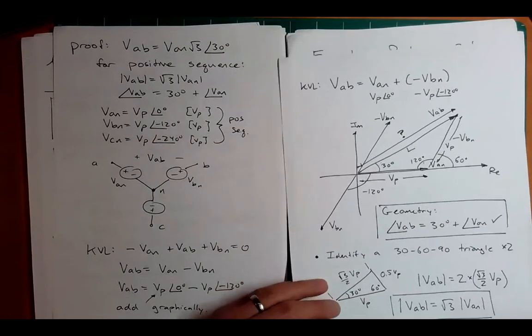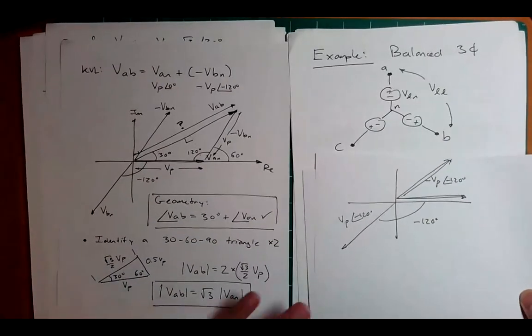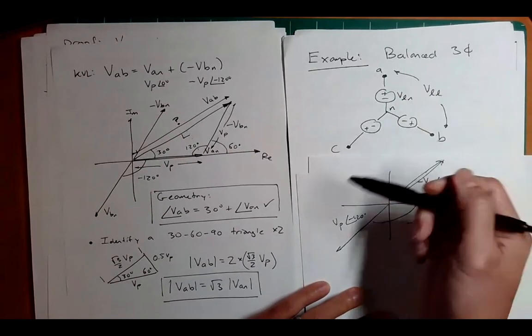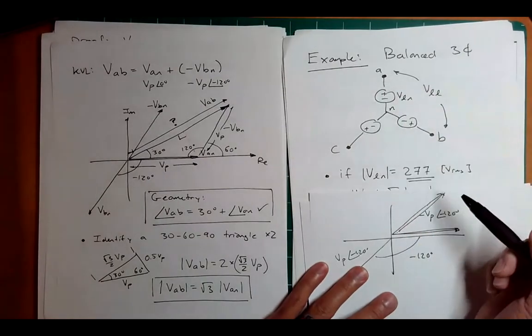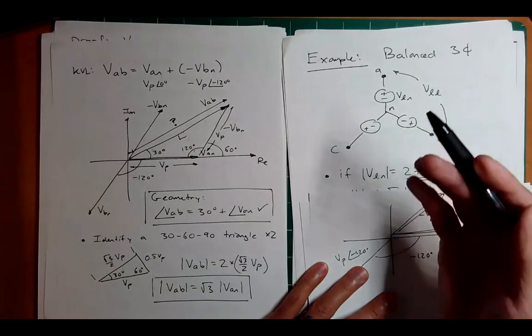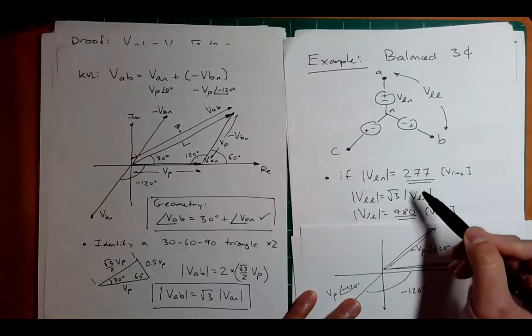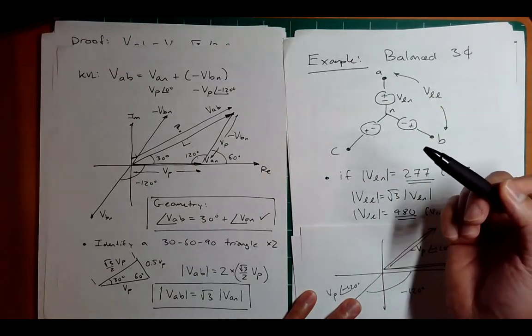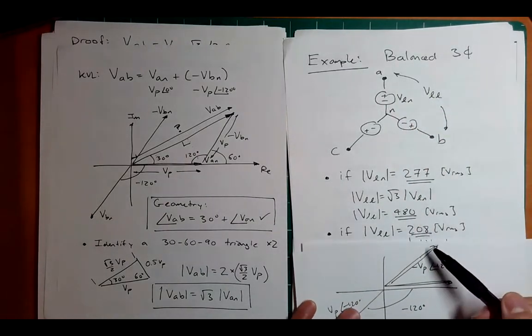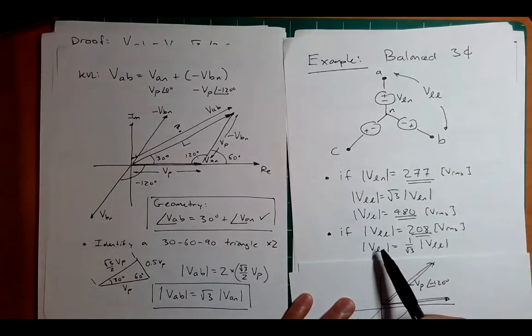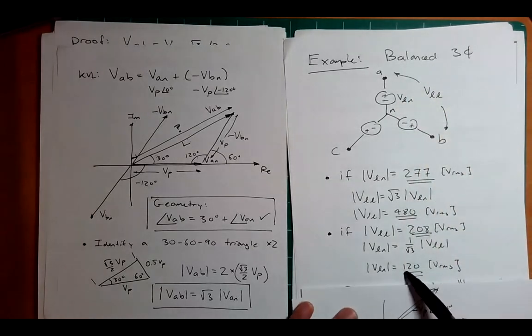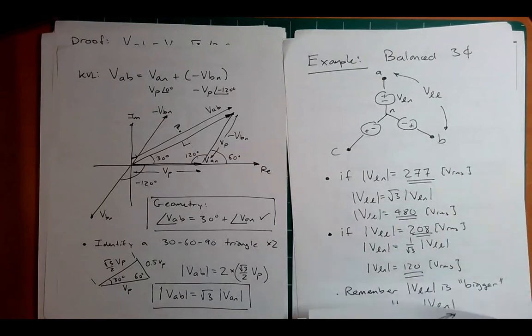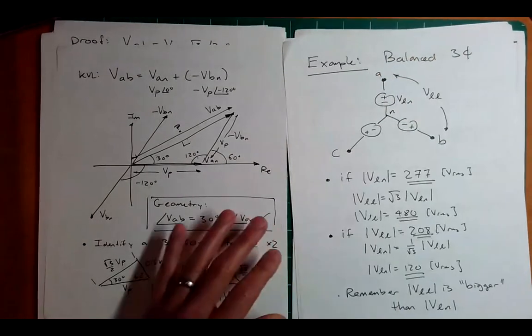The consequence of knowing this root-three relationship: if you have a line-to-neutral voltage of 277 V, you can easily calculate the line-to-line voltage — it would be root three bigger, approximately 480 V. If the line-to-line is 208 V, you do one over root three to get 120 V. So common voltages like 120, 208, 277, 480 all relate through root three. Always remember: line-to-line voltage is bigger than line-to-neutral.